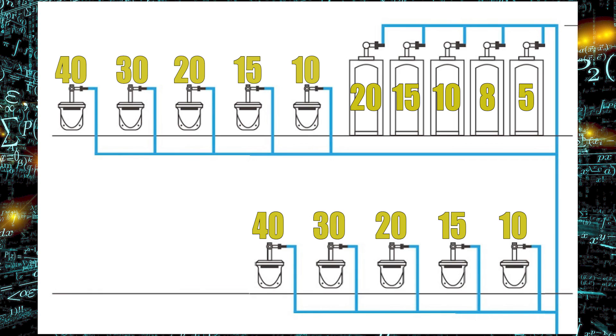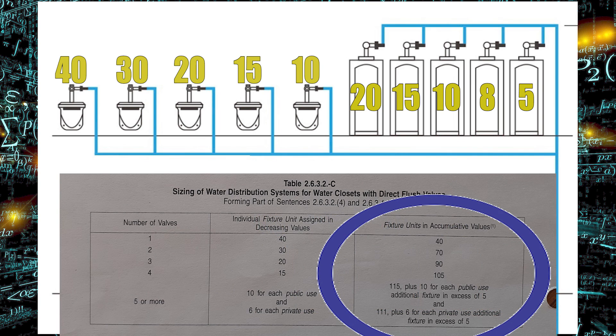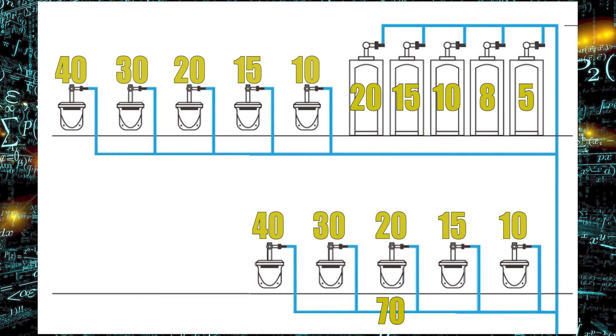Now let's look at those water closets on the top floor. Between these two water closets, we have 70 fixture units. Between this one off to the right, 90 fixture units. One more connection off to the right, 105 fixture units. And then the pipe that provides water to all five water closets is 115. Once again, I'm looking on table 2632C, and I'm looking in the cumulative values right on the right-hand side column. Now the water closets on the lower floor are going to look exactly the same as the ones on the upper floor once again.